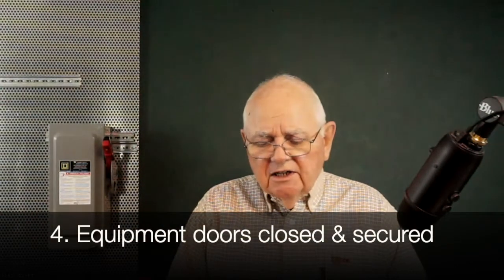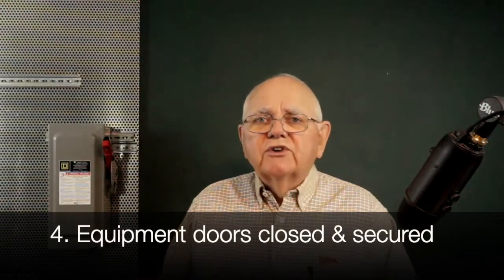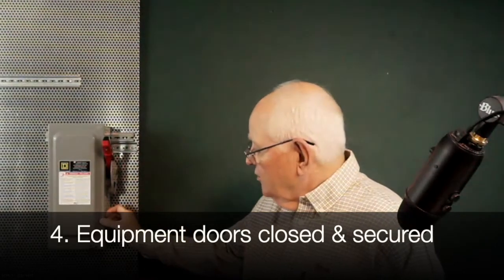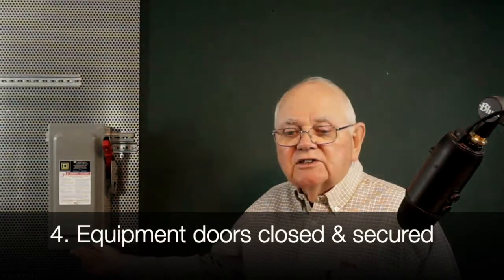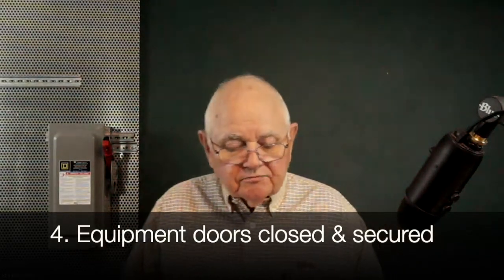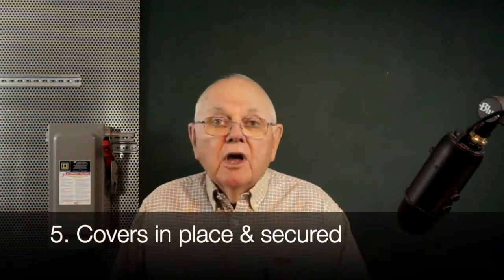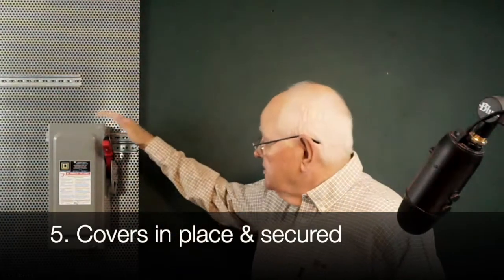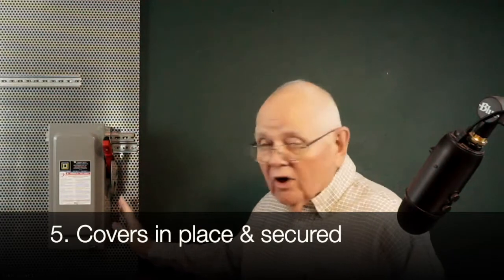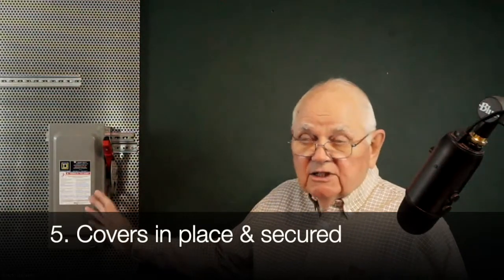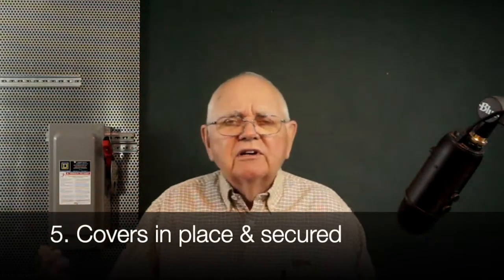Now, the fourth item says that the equipment doors are closed and secured. Well, we've got one door on a disconnect. It's closed right now and it's latched down here at the bottom. It says all equipment covers are in place and secured. Pretty simple. On the disconnect, all we really have is the door. If we had something like a switchboard or switchgear, maybe even control panels, we could walk around and make sure all the covers are in place and properly secured.